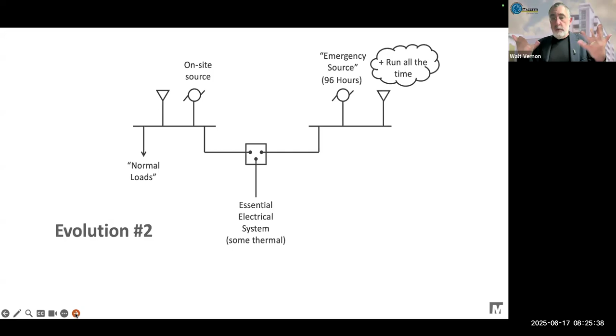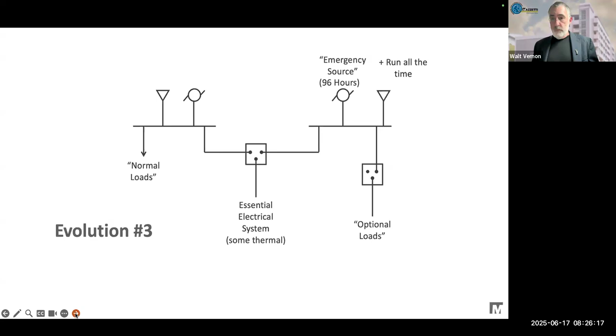Then we introduced the idea that you don't only have to feed the essential system loads from your backup source. Now you could serve any load you want from the backup source, as long as you segregated it from those loads required to have backup power. So now you could have a utility or an on-site source on either side of the transfer switches, either one can run all the time, and either one can serve any load in the building.